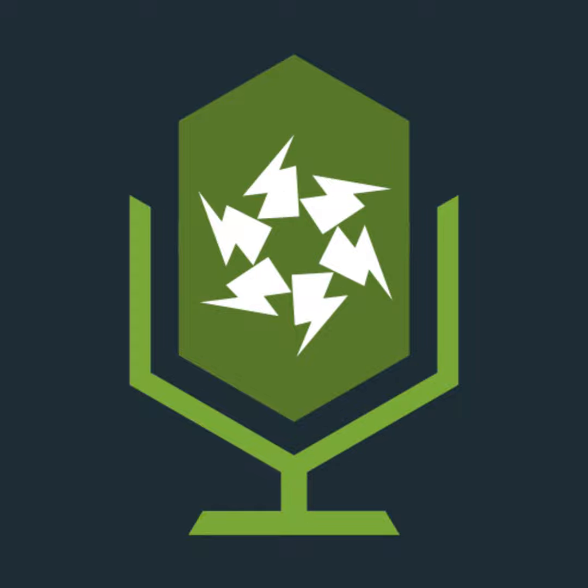I will just flag a couple of images to example this right now. I think good workmanship is great, and you should try your best to do that, but we do need to remember that if the designer has not said that this circuit is going to be bunched, we should not then bunch the circuit to make it look nice, okay? So the grouping table 4C1, page 396.